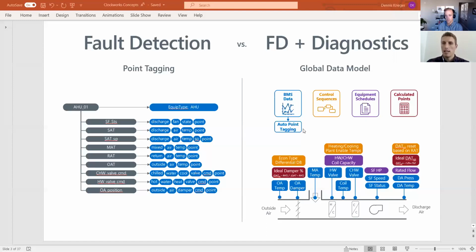You need to be bringing in variables from control sequences, equipment schedules, and even your own calculated points, things that don't exist in that controller but that you can produce using engineering equations, if you will, like calculating airflows and the ideal damper position based on known control sequences and equipment variables. So this is a hard line to me. I think there's a lot of fault detection software out there that can apply simple rules based on a clean tagged data set, but to really understand how your equipment is supposed to be operating, you have to get into this idea of a true data model.